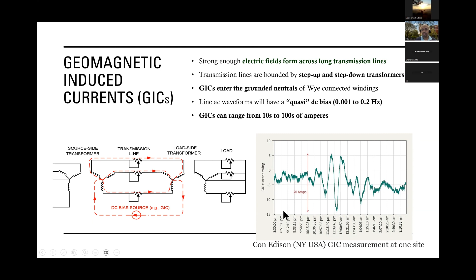So when did we first take big notice in the power system industry? It was when it hit the Quebec, Canada power system. That was the worst power disruption that's happened so far. In 1989, there was a geomagnetic storm that you might have been aware of, and it caused an over 8-hour blackout and many transformers to be damaged and overheated. Since then, there have been several events in South Africa, Sweden, New Zealand, and UK, where transformers were damaged, but none as bad as the Quebec, Canada scenario, which really woke up the industry to take notice that this can cause very widespread impacts to the power network.